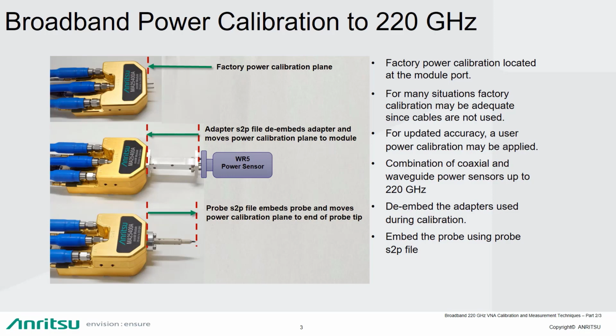And so what we would do is add our adapters to the module so that you can attach the power sensors for calibrations. So that would be both coax and waveguide sensors going up to 220 gigahertz. So you would have a coaxial adapter going up to 110, 125, and then add the waveguide adapters to add your waveguide power sensors. Then what that results in is, of course, you have shifted your power calibration plane to the end of your adapters, and what you now want to do is add your probe in order to make on-wafer measurements.